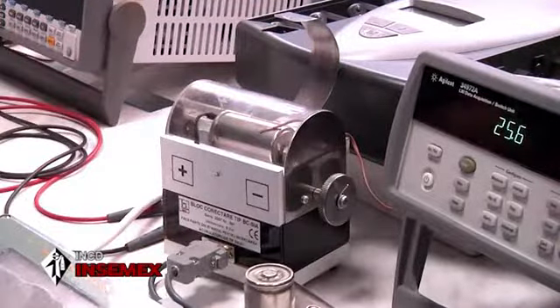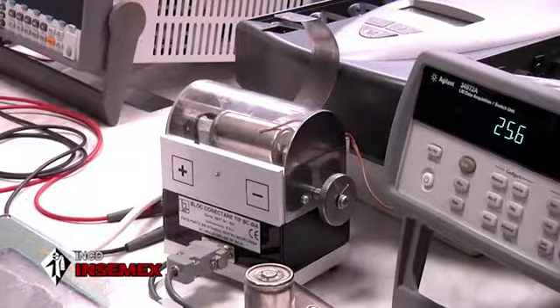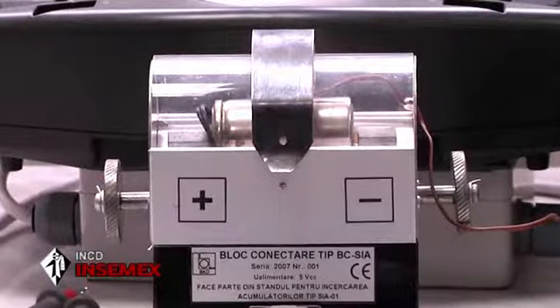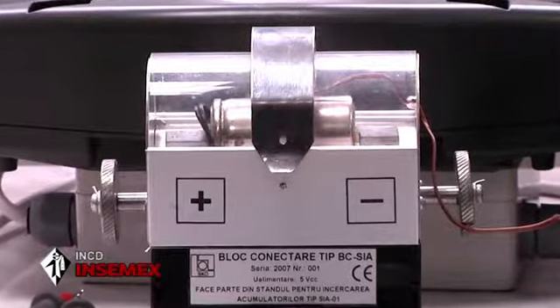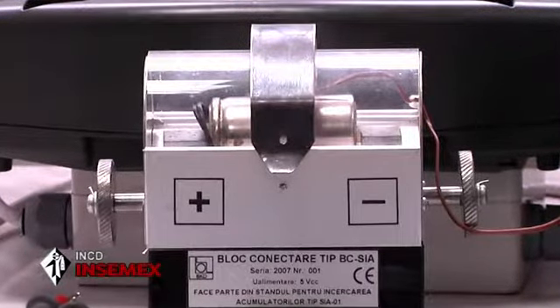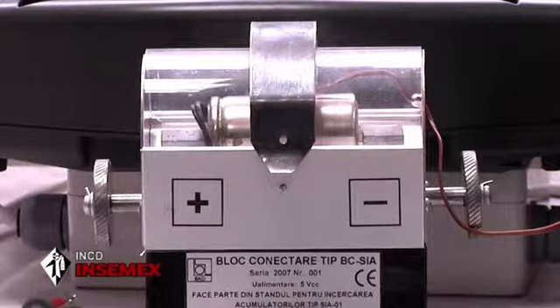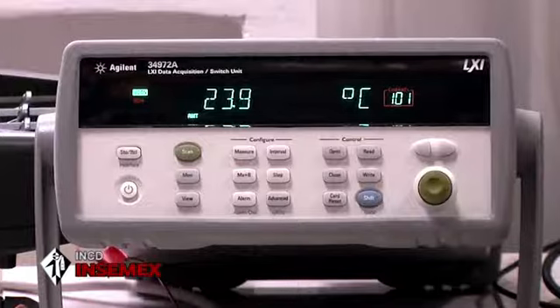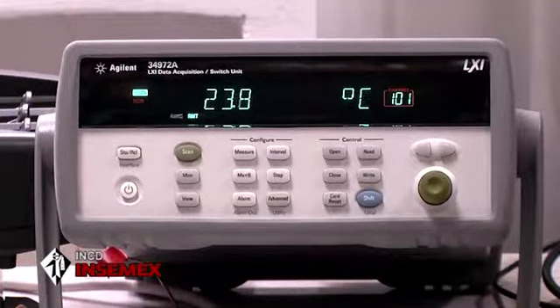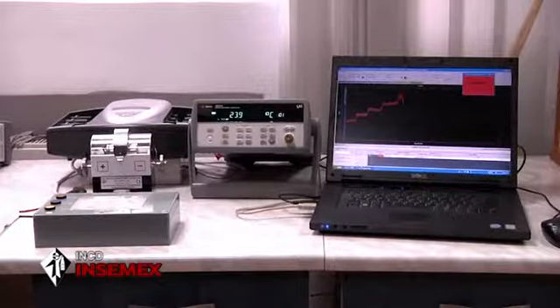During the test, the value of the surface temperature measured in the middle of the lateral surface of the tested component is monitored. The temperature peak obtained from recordings is corrected with the value of the difference of ambient temperature to the maximum ambient temperature of use. The maximum surface temperature value obtained, corrected for an assembly of 10 components, represents the final result of the test.